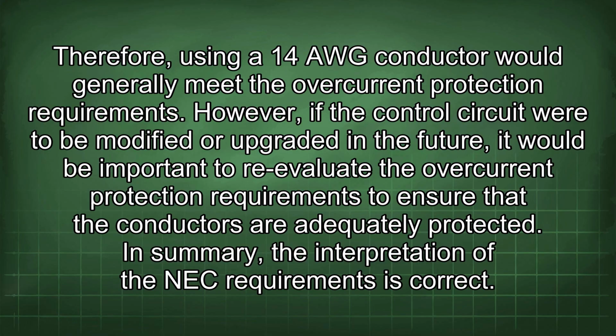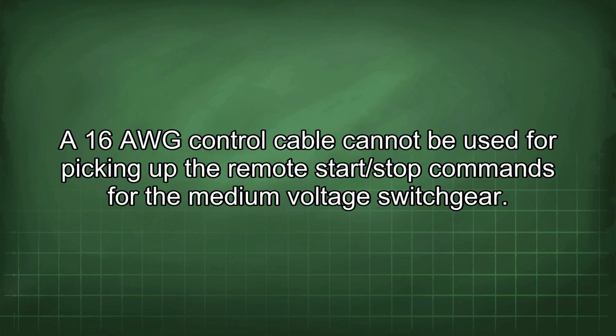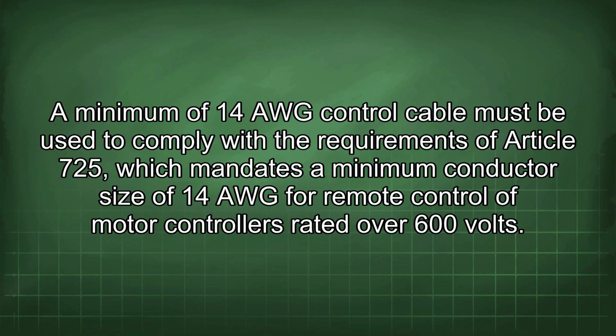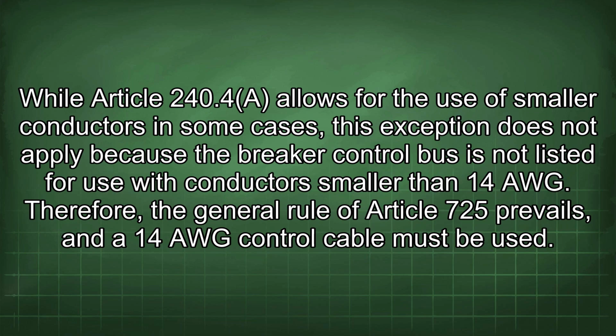However, if the control circuit were to be modified or upgraded in the future, it would be important to re-evaluate the overcurrent protection requirements to ensure that the conductors are adequately protected. In summary, the interpretation of the NEC requirements is correct. A 16 AWG control cable cannot be used for picking up the remote start/stop commands for the medium voltage switchgear. A minimum of 14 AWG control cable must be used to comply with the requirements of Article 725, which mandates a minimum conductor size of 14 AWG for remote control of motor controllers rated over 600 volts. While Article 240.4 allows for the use of smaller conductors in some cases, this exception does not apply because the breaker control bus is not listed for use with conductors smaller than 14 AWG. Therefore, the general rule of Article 725 prevails, and a 14 AWG control cable must be used.